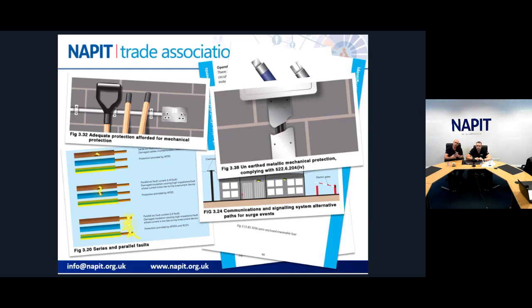But if you're using wiring in a zone, you also have to use a 30 milliamp RCD or mechanical protection, and the regulation we've quoted in that figure is mechanical protection, because it's not suitable to have a 30 milliamp RCD on meter tails to a consumer unit. If we did that, we'd be stepping on the toes of regulations requiring selectivity and diversity, splitting down different parts of the installation. One RCD up front stuffs us for that, so this method allows us to adequately protect the cable and think about division later at the consumer unit.